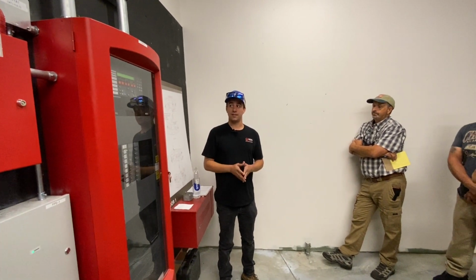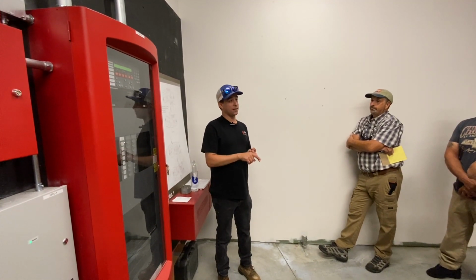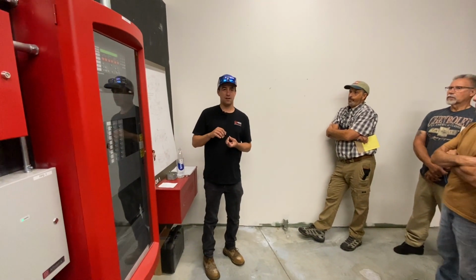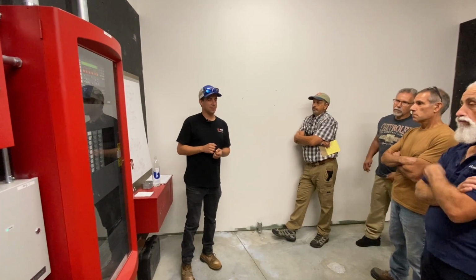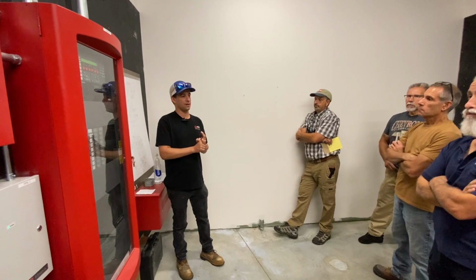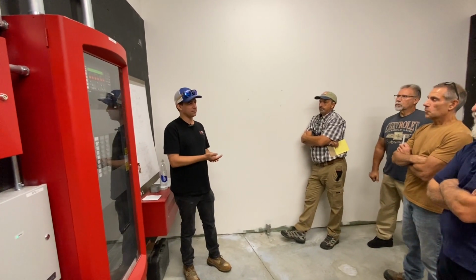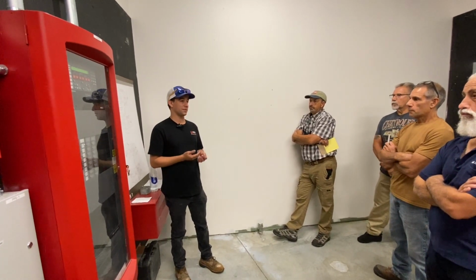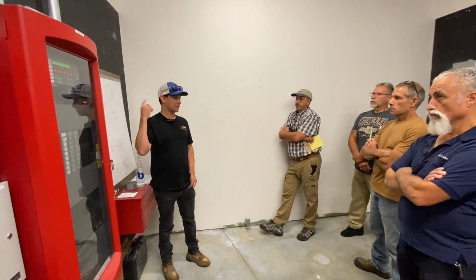The other things you may see on the panel on a regular operating day might be supervisories or troubles. Supervisories are like a manipulation is happening, but it's usually something caused by somebody, or something just below a fire alarm type of event. Like, do we have CO detectors in the building? Correct. A CO detector doesn't come in as a full-blown alarm. It comes in as a supervisory. It probably does not alert the entire building.